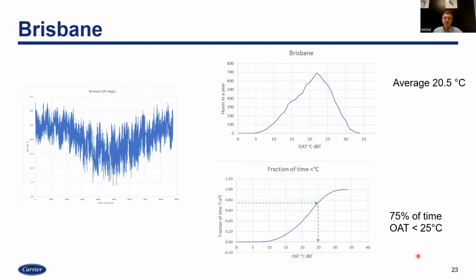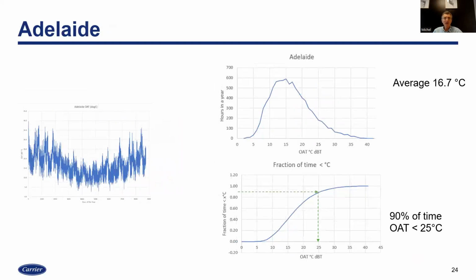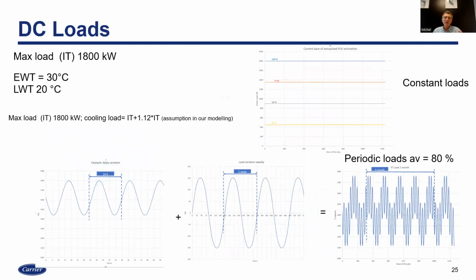In Brisbane, only 75%, so it's hotter, but still significant. It's not like Adelaide at 90%, and not like hot countries such as Australia where we imagine there's no potential for free cooling. If you start to have high temperature water loops, which is the case for data center applications but not for air conditioning, then you may have a significant amount of free cooling.